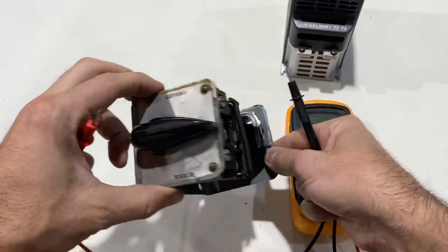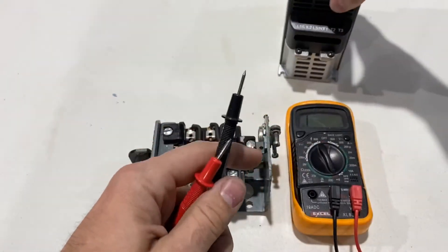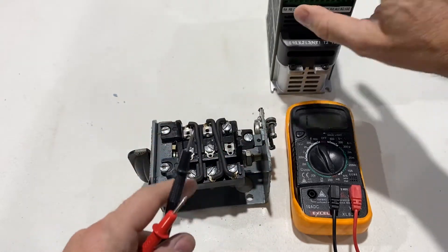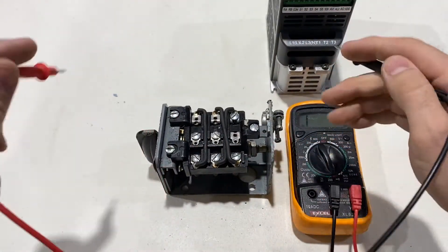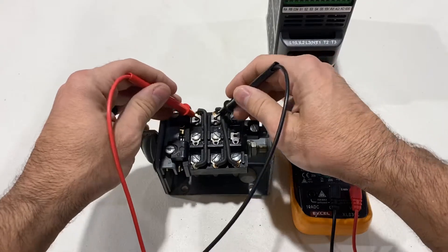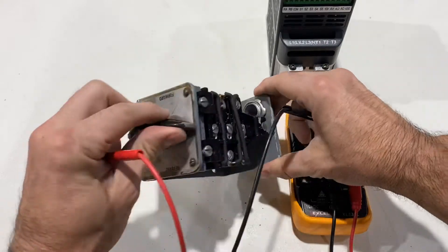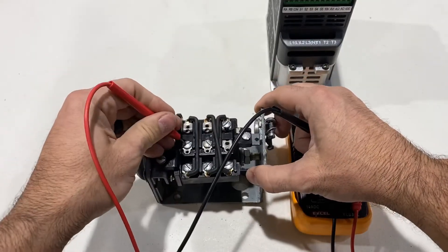Right now we have the switch set to off, and we have to find a common, because for your VFD you'll need three wires: common, switch one, and switch two. I'm not going to get into setting the parameters of the TECO-Westinghouse specifically because your VFD may be different. We just need to go through the process of finding a common. Set your switch to forward and it's just a process of probing around.